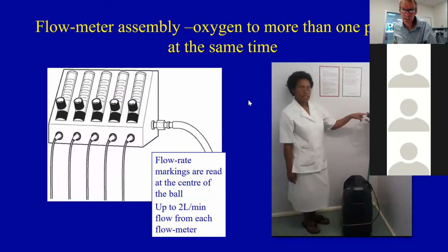Okay. Now, finally, for some places, I want to talk a bit, very briefly, about these flow meters, because they have some in children. When we're giving oxygen, in some hospitals, we've set up these flow meters, and the flow meter attaches to the concentrator. So the concentrator puts oxygen into the flow meter, and then that divides up the flow, and it can divide it up between 1 and 5 patients. And that means for a 10 litre per minute oxygen concentrator, you can perhaps give 2 litres per minute to 5 different children, or even 5 litres per minute to one, and 1 litre per minute to another, and 2 litres to another. And you can dial up an individualized flow. And I think that's the way we've set it up for children.